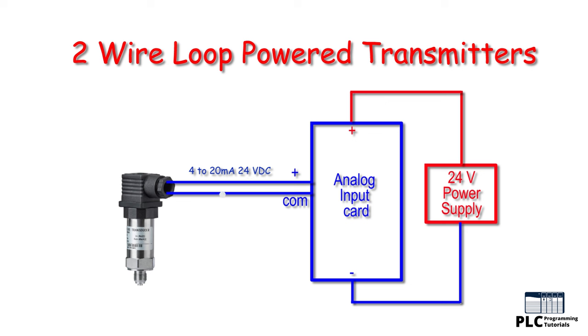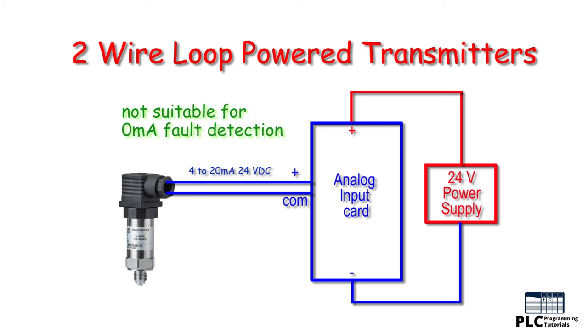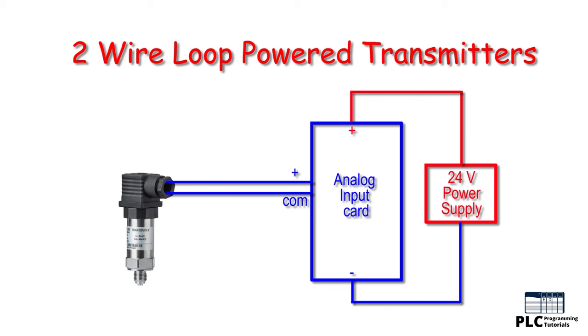This configuration also has some disadvantages. Transmitter discrete fault signaling cannot be set at 0 milliamps, as this configuration continues to draw some current in a fault condition. Therefore, this configuration is not suitable for control panels that require a 0 milliamp signal for fault indication.